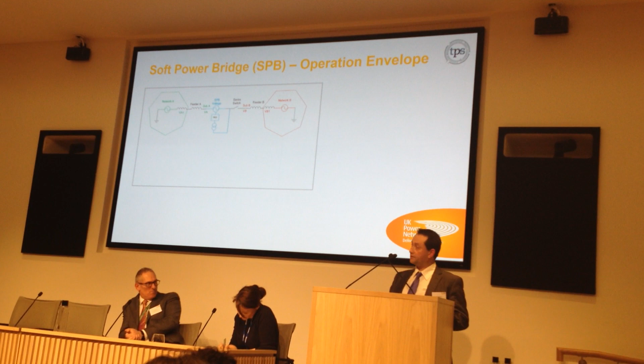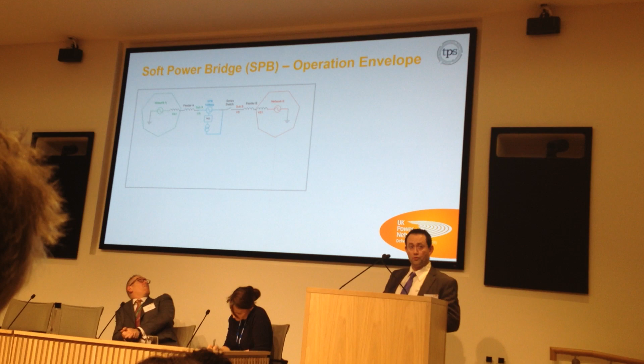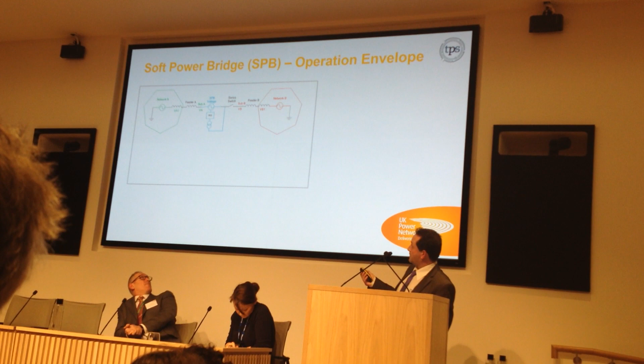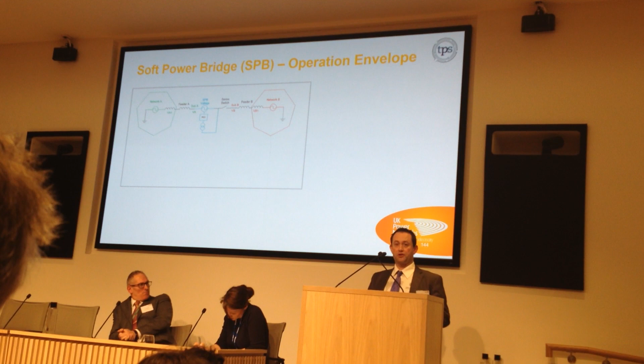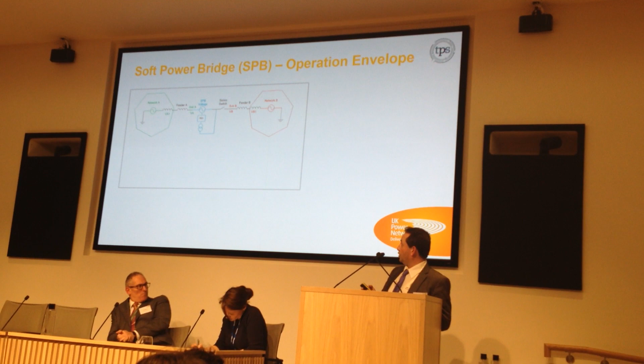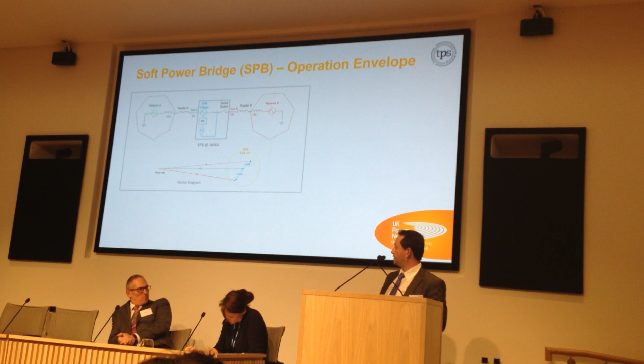So first of all, here is effectively the same at the 11 kV level that we had for the soft open point. We can see here we've got two networks, network A, network B, and we're meshing with the device in the middle. That device comprises the power electronic converter, an auxiliary transformer, but you can see it's in parallel with the network. Because we're very sensitive at 11 kV to protection, we need to protect the device, we have a series switch which is actually a solid state device. So again, this is semiconductor technology. Now the way this system works, it works on controlling voltage vector. Voltage vector in both magnitude and phase, unlike the soft open point, which is a full power transfer system. So that has its limitations, and I'll just quickly talk through these.